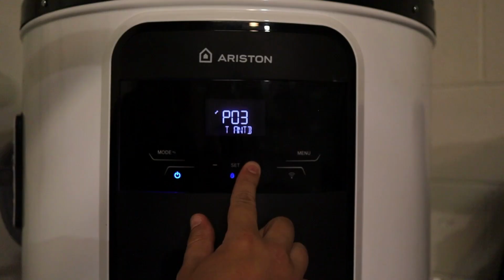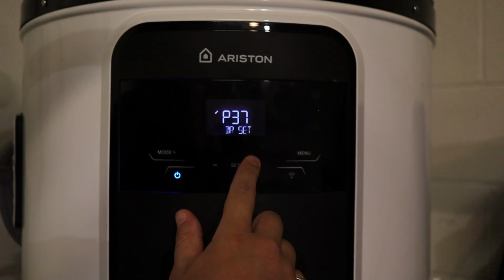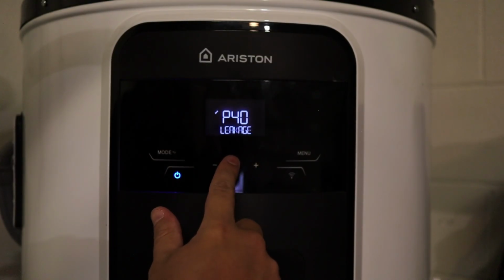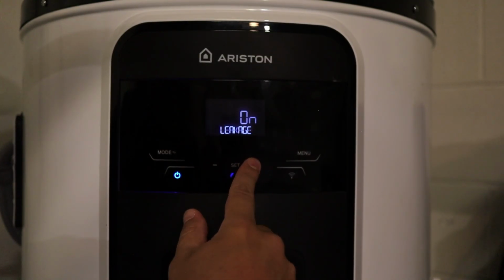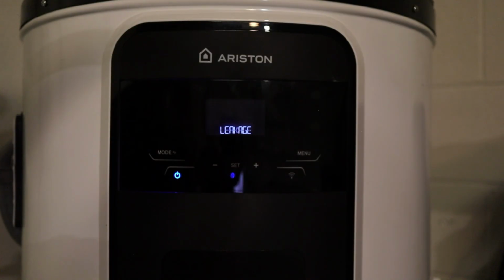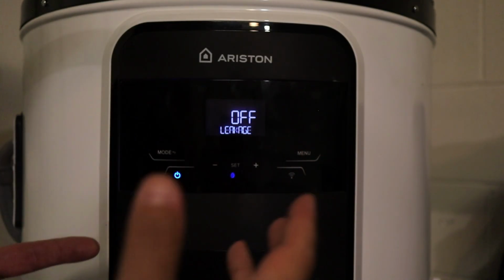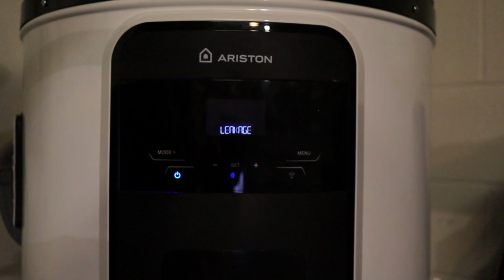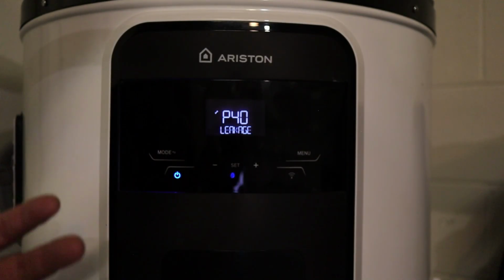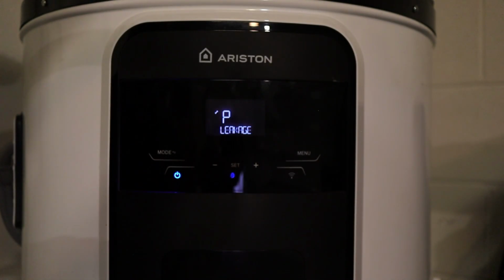We're going to go ahead and go all the way up to P40. P40 is going to be our parameter for our leak detection sensor. Go ahead and hit set. Leak sensor right now is on. We can change that to off. So if we don't want the system to interact with the leak sensor at all, we can change that to off. So if you're waiting for a new leak sensor to come in, or you just don't want to deal with the leak sensor at all, you can go ahead and change P40 to off. And then once you get the new leak sensor in, just go ahead and make sure you turn that P40 back to on. But essentially what we're trying to do is stop you from having a no heat situation where you're waiting for a part. We can go ahead and shut that off in P40.